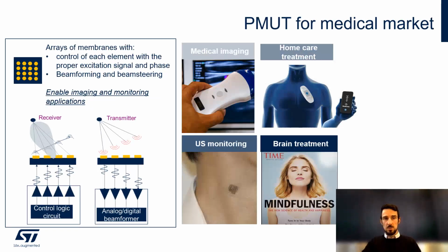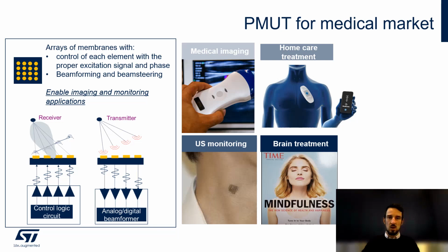So keeping the same concept, but by reducing the membrane dimension, higher frequencies can be used, and this allows many applications in the human body with better resolution. Applying the transmission and reception concept seen before to an array of membranes, together with the proper electronic excitation and processing, the shape of the acoustic wave, which now becomes an acoustic beam, can be designed as needed. So this enables, of course, the well-known medical imaging application to be served by PMUT with MEMS technology.